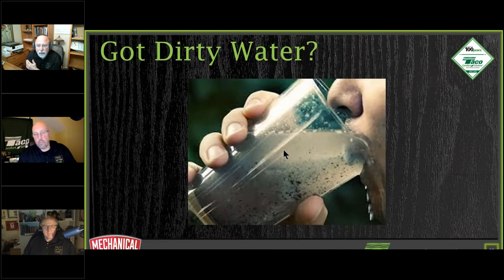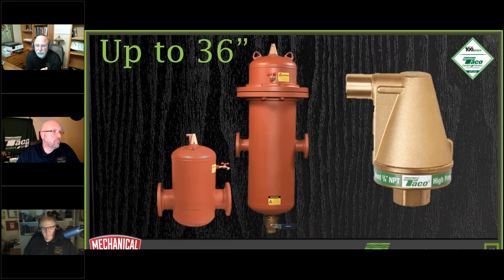Hey, Dave. Yes. Sean's got a question that somebody else had asked already, and I just typed him an answer, but I'll say it in case anybody else is going to ask. They're asking about putting a ball valve on each side of a 4900. Well, if you want to add that much, it's not required. If you want to add that for serviceability, absolutely. You're just adding a lot more man hours and more money for those inch and a quarter, inch and a half ball valves. So the answer is not required, but if you want to put more valves in there, go for it.